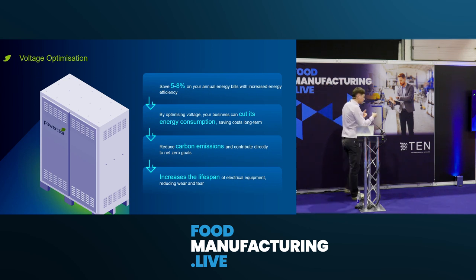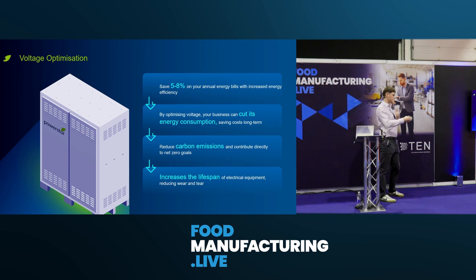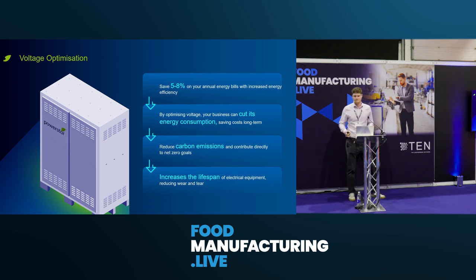By making this equipment run more efficiently, we then start making it use less energy, less heat, less wear and tear. So as we know, bearings, motors, oils, the warmer they get, the less lifespan the devices have. By reducing this and making it more efficient, the heat loss goes down, the bearings run longer, switch mode power supplies work better as well, so the drives and the inverters also see a benefit from this. Carbon emissions comes hand in hand with the energy saving. So if you're on a green tariff already, you don't get any carbon savings. But if you're still importing energy on non-green tariffs or in non-green periods, then you'll get the carbon savings via the reduction in kilowatt hours.